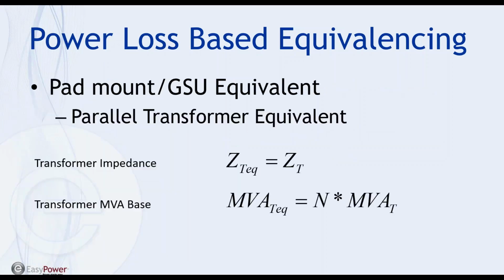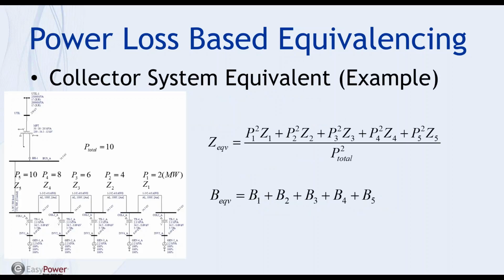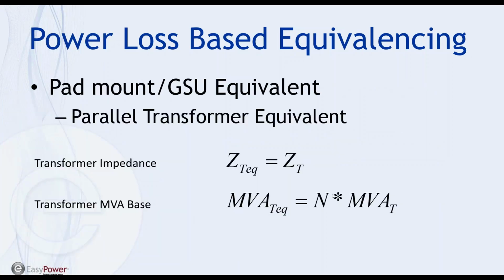then we can get the impedance of our collector system equivalent. Now, about the pad-mount transformer and the GSU equivalent, the theory is much simpler. You can just imagine that the equivalent transformer is the transformer equivalized by a series of parallel-connected transformers, right? So if you have, let's say, 5 transformers connected in parallel, the impedance would be 1/5 of the impedance of each one of them. And if we recall our per unit theory, we don't have to change the impedance, we just need to raise the MVA base of the transformer by n times. N is the number of transformers connected in parallel. Then I got my parallel transformer equivalent, right?